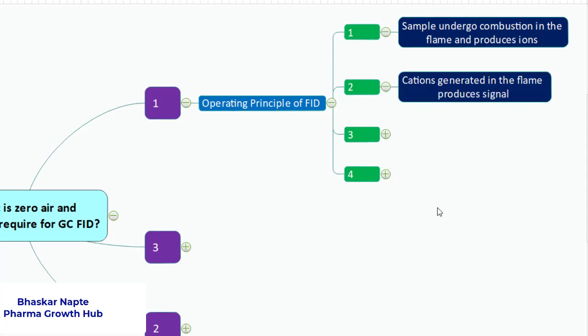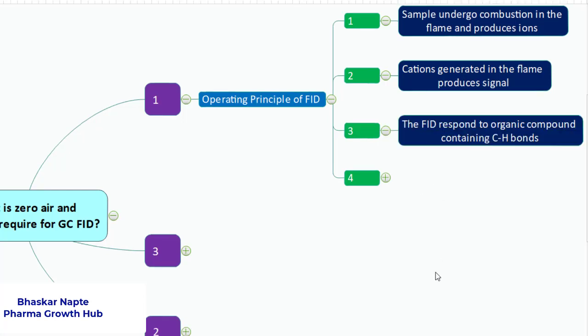The cations generated during the combustion in the flame are responsible for producing the signal. The FID responds to organic compounds containing carbon-hydrogen bonds or hydrocarbons. This is a very specific detector which predominantly responds to carbon-hydrogen containing compounds or hydrocarbons. It can be, let's say, methanol contains carbon-hydrogen bonds, ethanol contains carbon-hydrogen bonds. So these organic compounds FID responds very well.